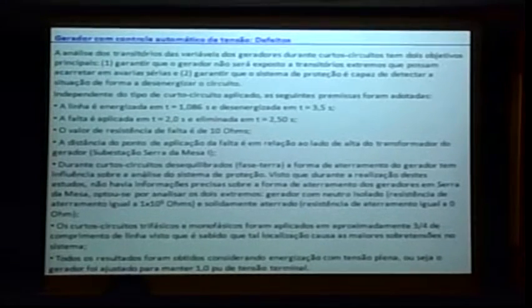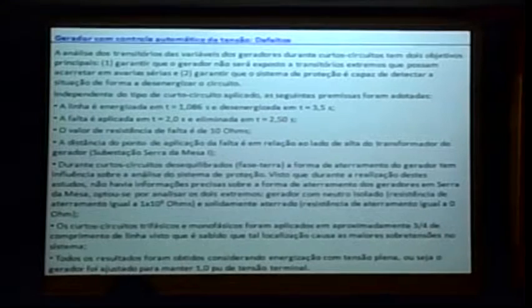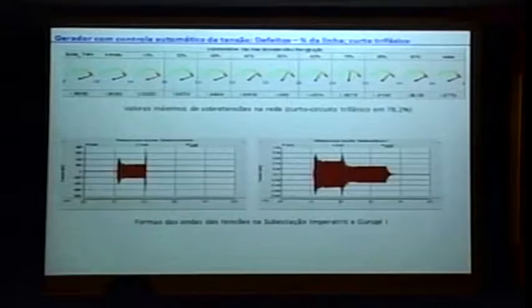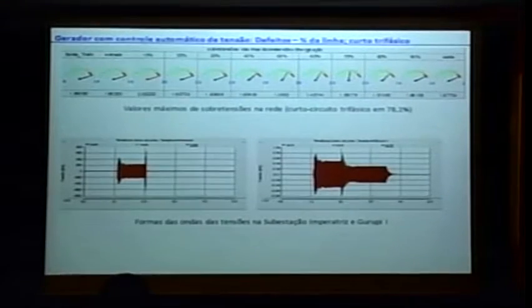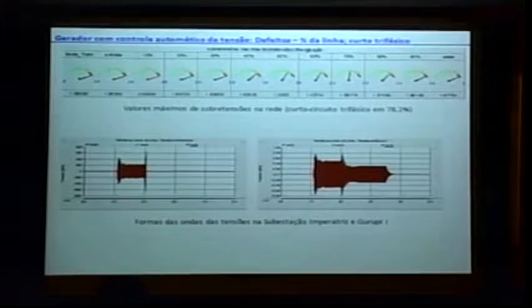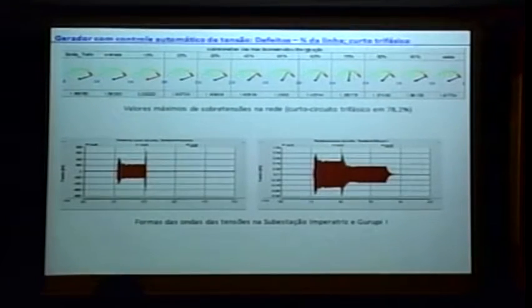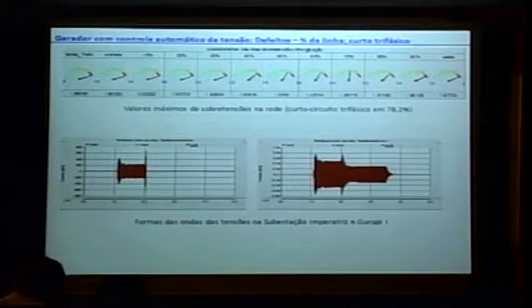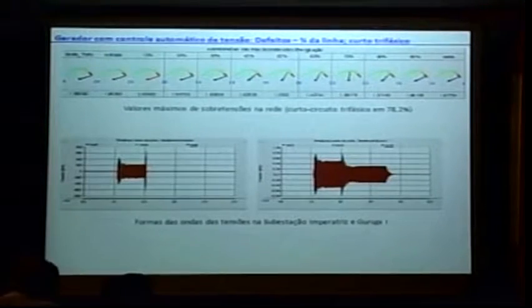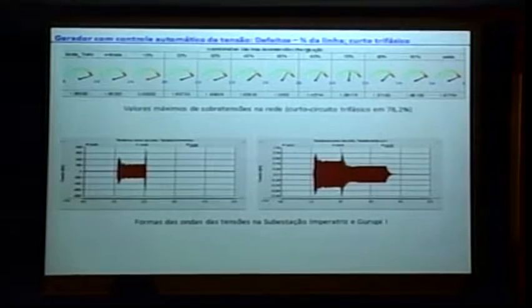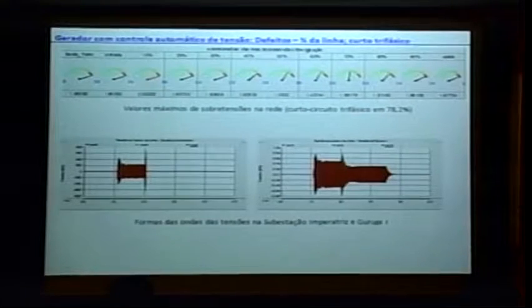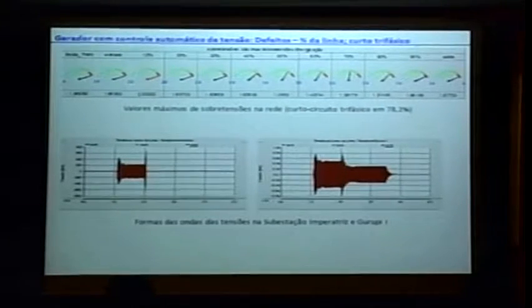Let's go on and see the results. I've spoken about all this. The voltage of the generator, 1 pu, in this case here. And then we also had the study with the reduced voltage. Now we have short circuit, 3-phase fault in 3/4 of the line. Here are the over voltages that appear in each point of the line.